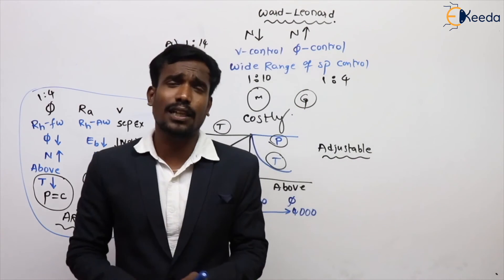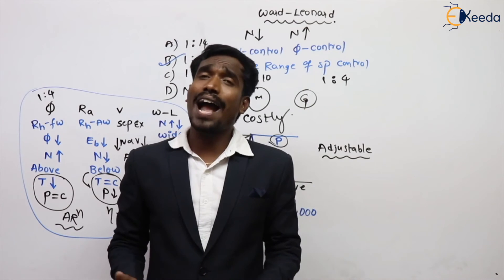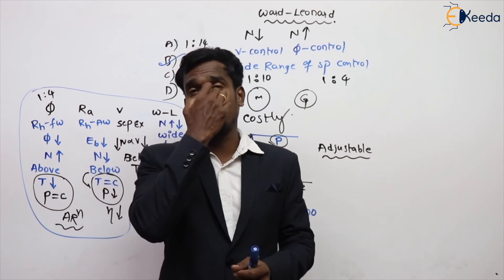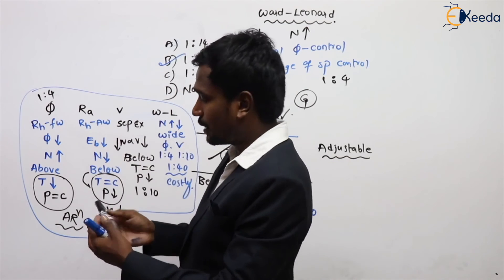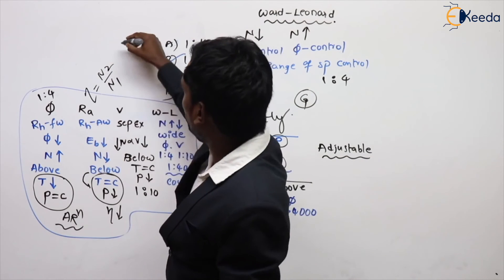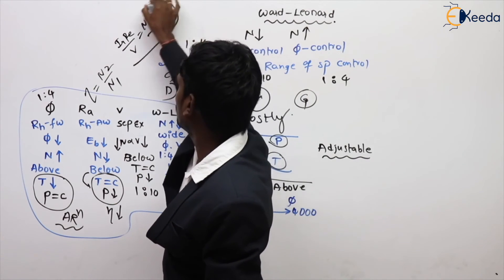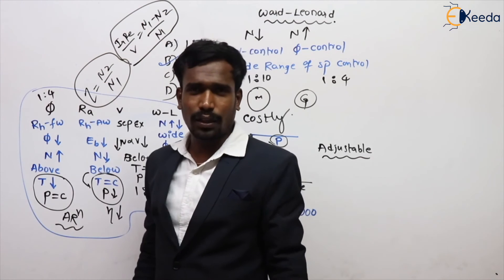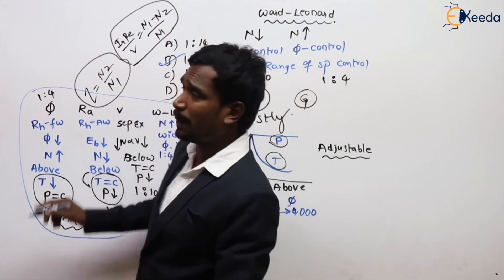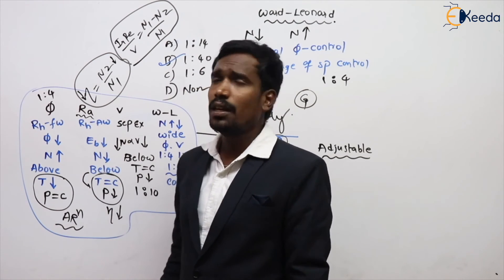What is the disadvantage of armature resistance control method? In this method, if you want to change the speed, you have to add extra resistance in series to the armature, through which armature current flows. So power losses increase in the machine, which reduces efficiency. The efficiency formula is N2/N1, and another formula is Ia×Ra/V, which equals speed regulation. When speed reduces enormously, efficiency of the machine also reduces, and extra heating effect occurs. These are the disadvantages.